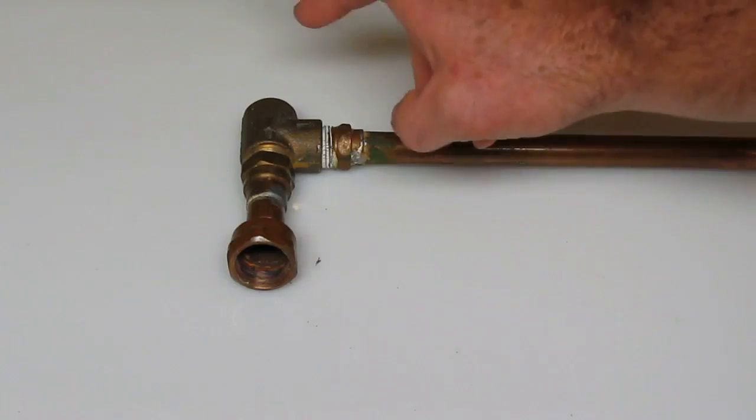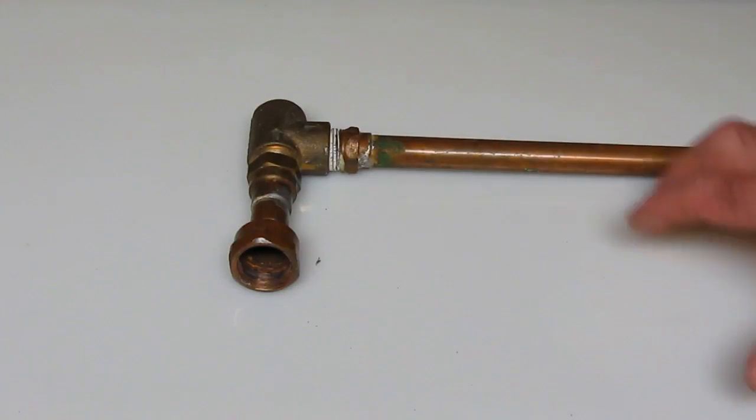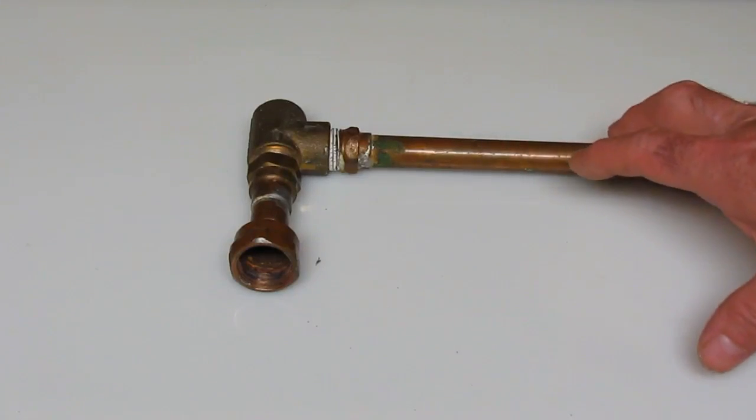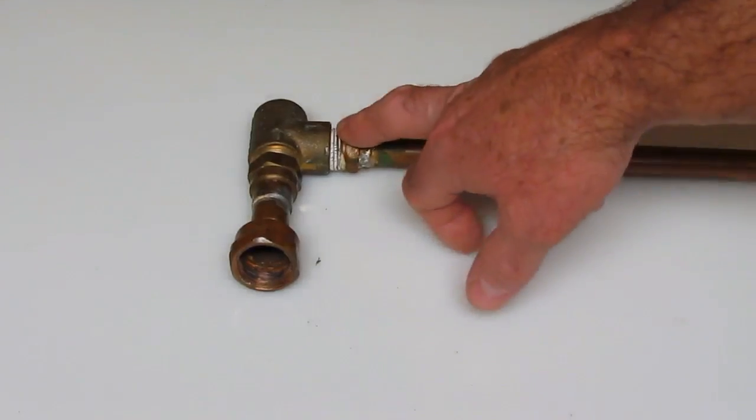And if a relief valve is leaking, don't plug it. There's a reason that it is leaking. You're basically talking about having a bomb is what you're having there if you plug a relief valve off.